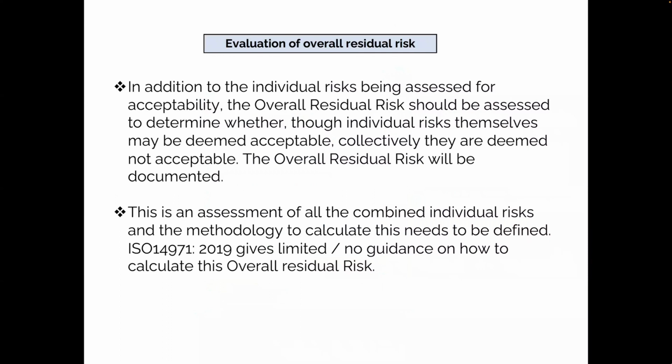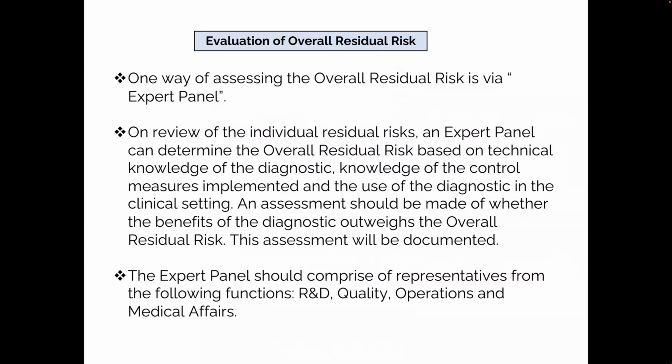However, the standard gives no guidance really on how you do that in terms of overall residual risk. And it's not as easy as just doing an average, because you can't really do averages of some of these RPNs. It's not really appropriate. So one way to do it is by what I call an expert panel. Basically, you get an expert panel with representatives from the cross-functional team and clinicians who have an intimate knowledge of the diagnostic, know the control measures, and know the state of the art of the device and other devices, and they make an overall assessment of the residual risk of the device and document that.